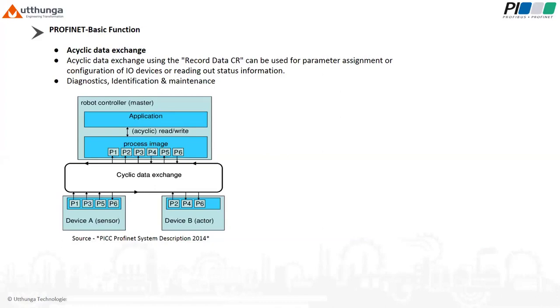Acyclic data exchange using the record data communication relation can be used for parameter assignment or configuration of IO devices, or reading out status information. This is accomplished with read or write frames using standard IT services via TCP/IP. The image shows acyclic and cyclic communication, how it's happening. Using cyclic communication, we are talking to the devices, sensors, while acyclic communication is used for configuration and parameterization, and I can read or write, or using a supervisor I can configure whichever devices the controller needs to talk to in a cyclic manner.